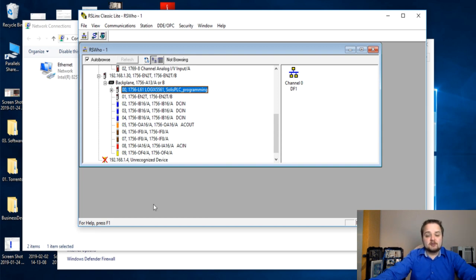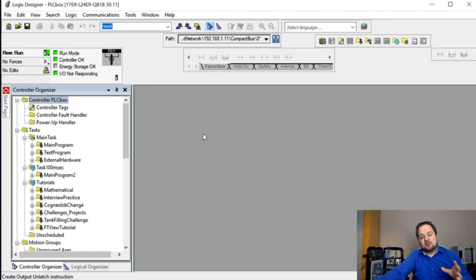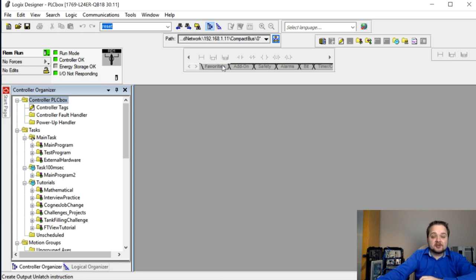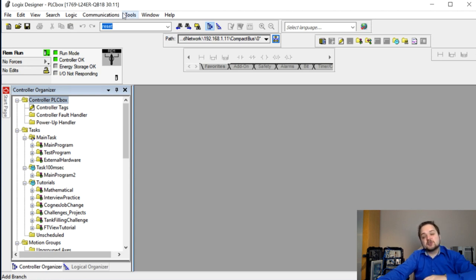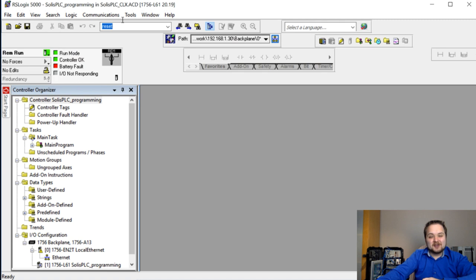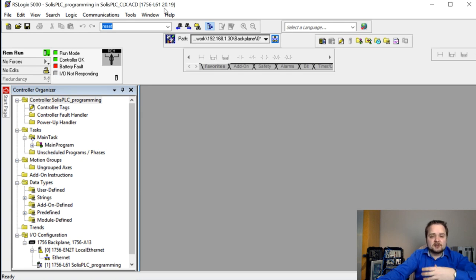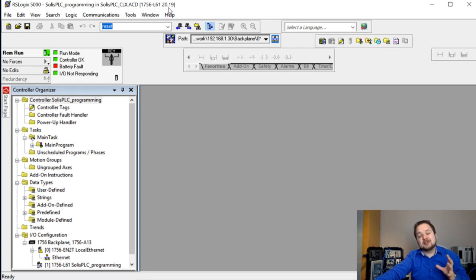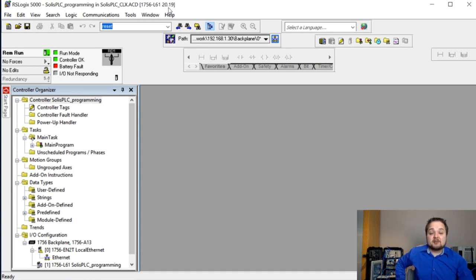We'll launch RS Logix and Studio 5000 to set up communication between the processors. We're connected to both controllers. The CompactLogix at .11 is running firmware version 30.11, which means it uses Studio 5000. The ControlLogix 1756-L61 uses the older RS Logix 5000 at version 20.19 - that's the latest version you can flash on that controller. To use Studio 5000 you need the L71 processor.